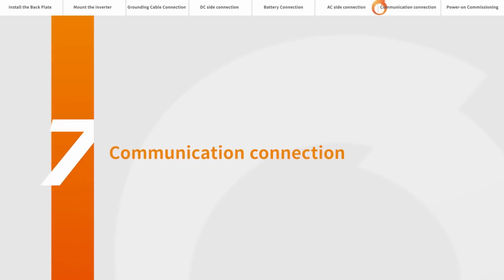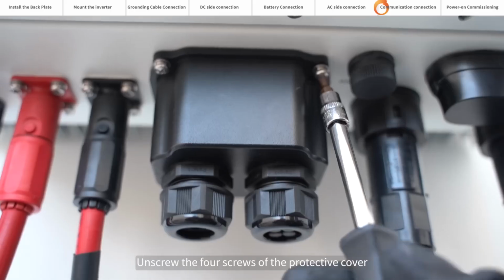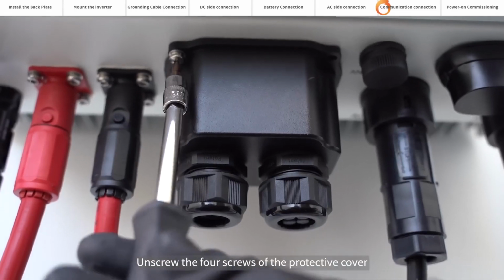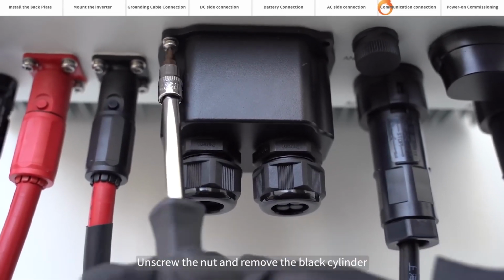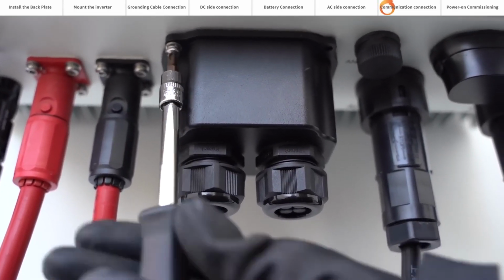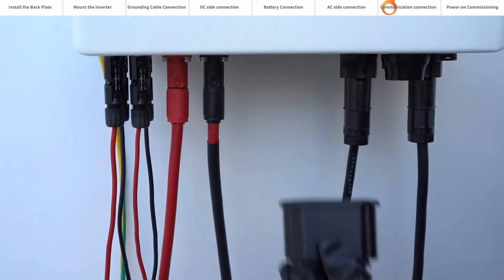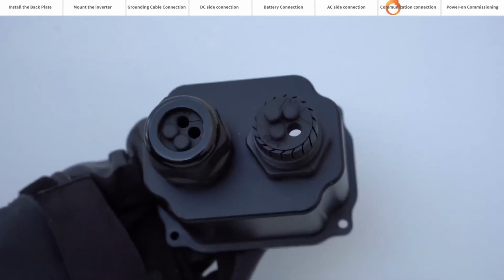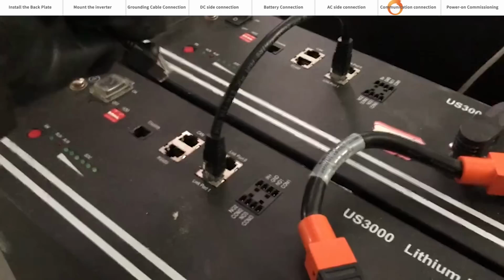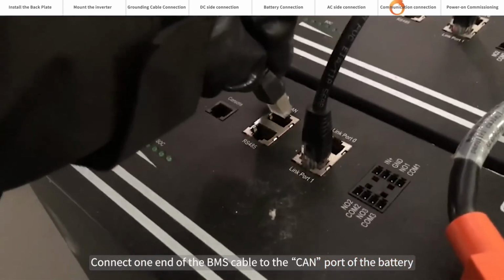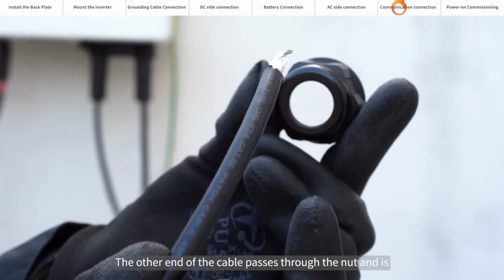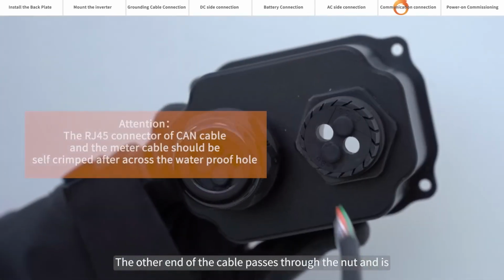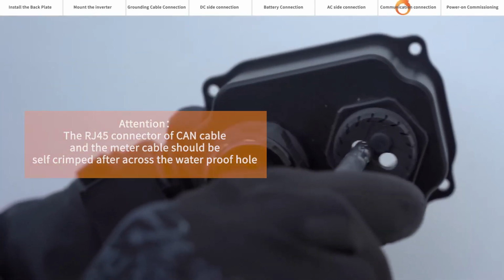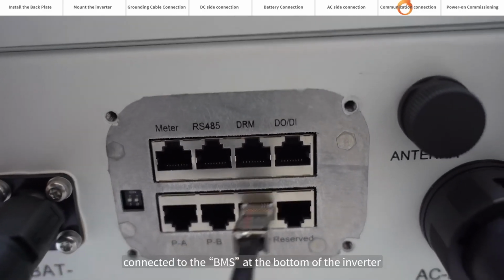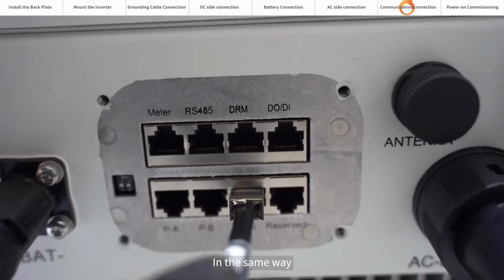Communication connection. Unscrew the 4 screws of the protective cover. Unscrew the nut and remove the black cylinder. Connect one end of the BMS cable to the CAN port of the battery. The other end of the cable passes through the nut and is connected to the BMS port at the bottom of the inverter.